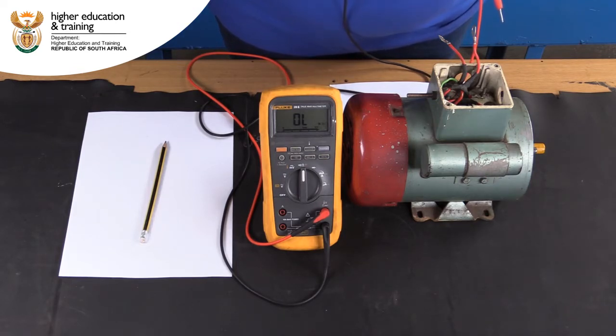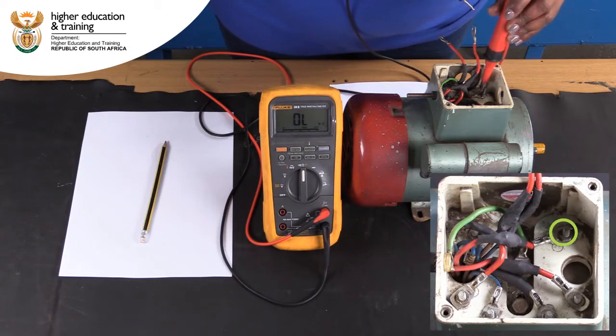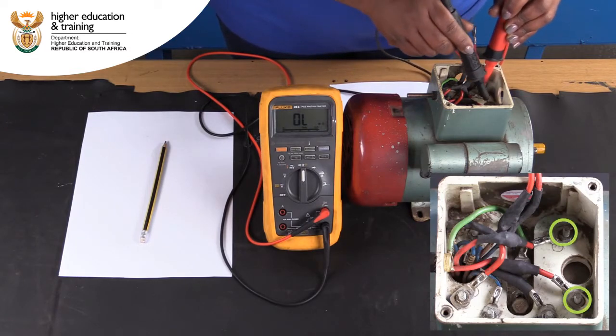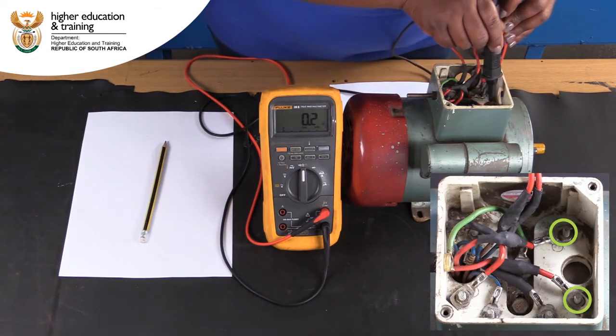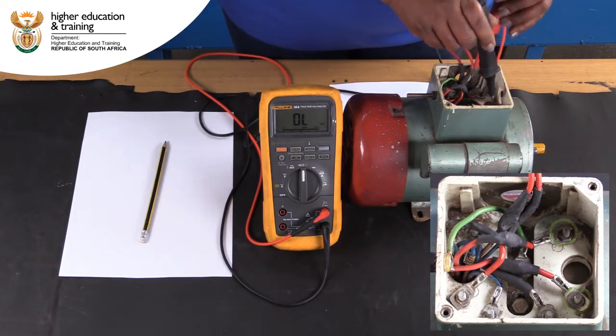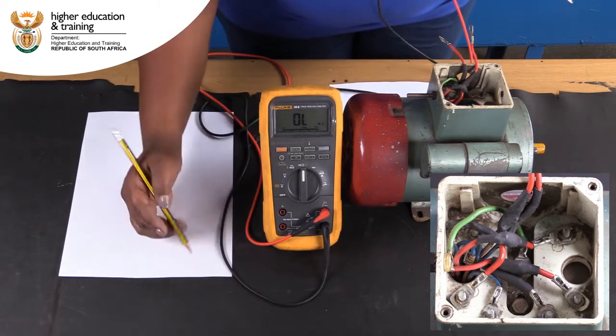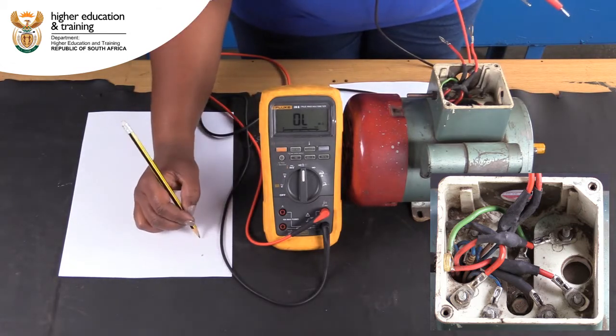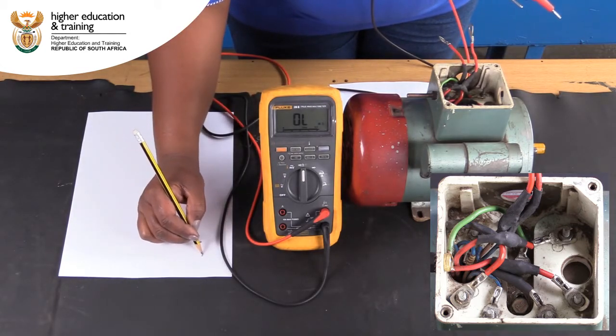Now we start to measure the resistance between the different posts. Between posts 1 and 2, we get a reading of 0.2 ohms. This near-zero reading indicates the centrifugal switch. Make a note of this result on your own terminal block diagram.